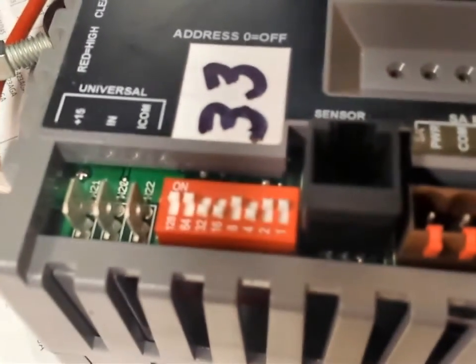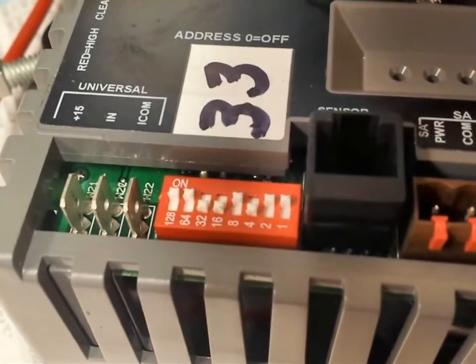Now here we have the jumpers for this device. This is where you're going to set the address. You have to set these jumpers correctly. If you do not set them correctly, using CCT, the program is not going to even load to the device. You have to have the jumper set for the address for the device that you're going to be replacing, as well as the address must match that address in the programming. Some of your older programs like HVAC Pro and all that will allow you to push programs to different addressed devices. CCT will not. So you must have the correct address set on these jumpers.